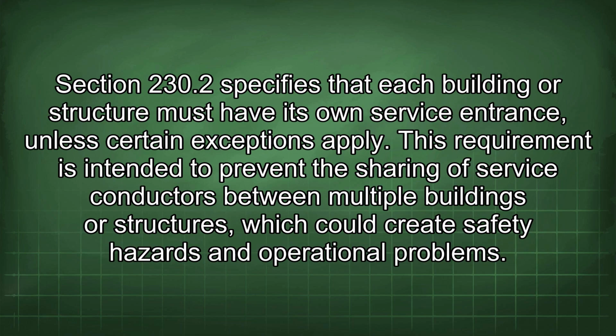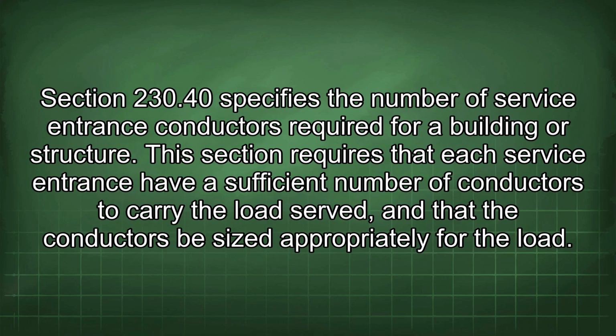Section 230.2 specifies that each building or structure must have its own service entrance, unless certain exceptions apply. This requirement is intended to prevent the sharing of service conductors between multiple buildings or structures, which could create safety hazards and operational problems. Section 230.40 specifies the number of service entrance conductors required for a building or structure. This section requires that each service entrance have a sufficient number of conductors to carry the load served, and that the conductors be sized appropriately for the load.